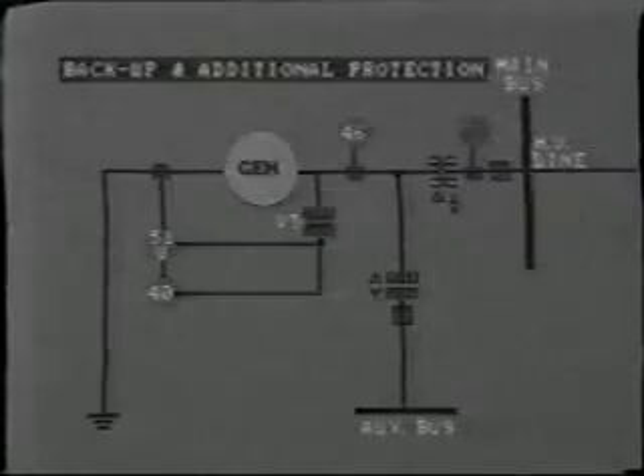Usually, a breaker pole failure relay, device 61, is installed where the system configuration makes this type of failure possible. The 61 relay operates by comparing the balance of current in the three phases on the primary side of the unit transformer. The relay will operate if one phase current is low, while either of the other two is high, by a ratio of 1 to 3. When the relay operates, it de-energizes the excitation circuit of the generator.